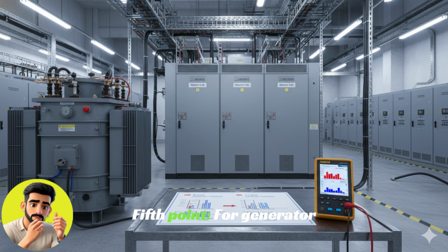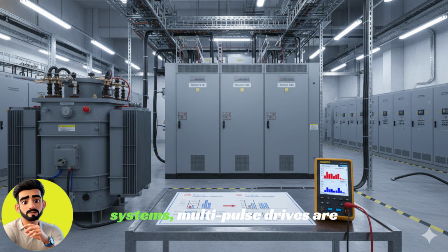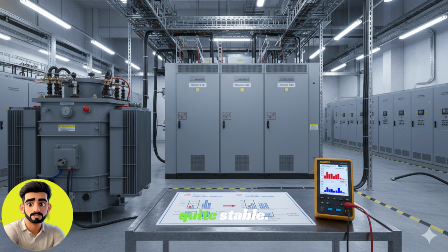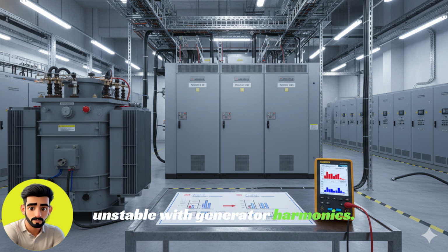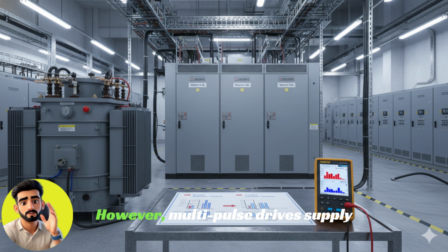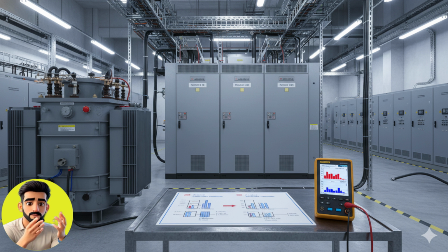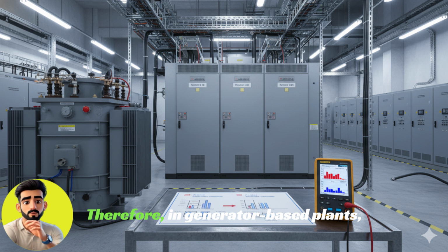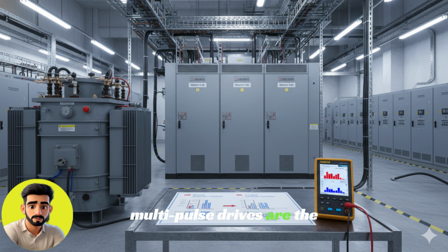Fifth point. For generator systems, multi-pulse drives are quite stable. Normal drives tend to become unstable with generator harmonics. However, multi-pulse drives supply clean current to the generator. This keeps the frequency stable, voltage stable, and hunting almost zero. Therefore, in generator-based plants, multi-pulse drives are the best choice.